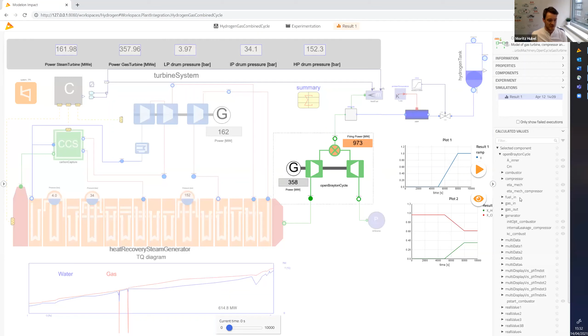So we can, for example, look at the exhaust of the gas turbine and see what's coming out. One of the main effects is that the composition of the flue gas will change. Here I plotted the water content in brown and the CO2 content in purple. As you can see, increasing the hydrogen content gives a significant reduction of CO2, which is the good point—that's what we actually want to achieve with the hydrogen economy. So that worked out, that's fine.